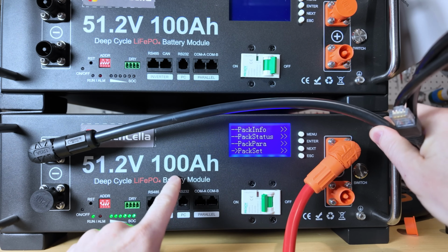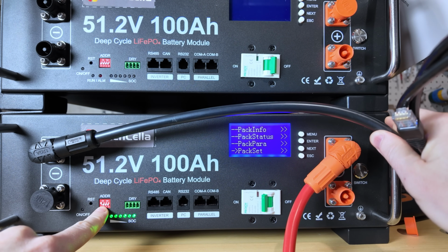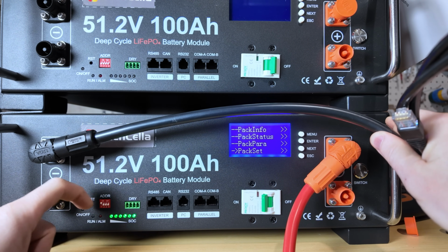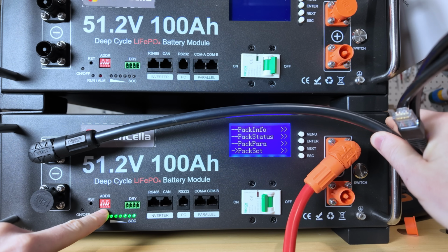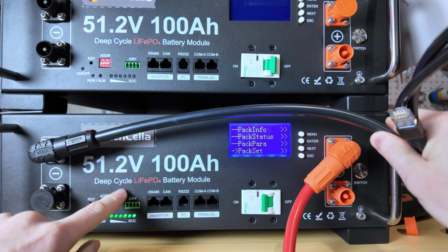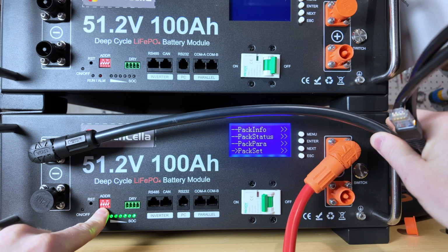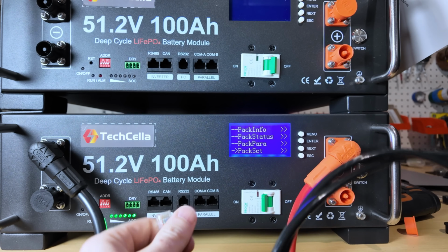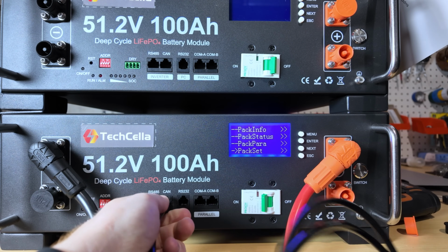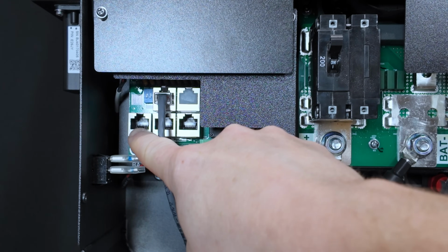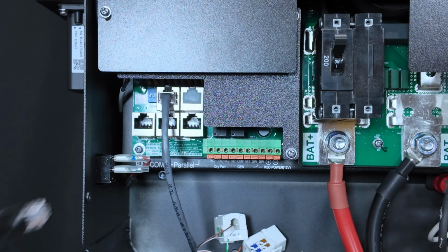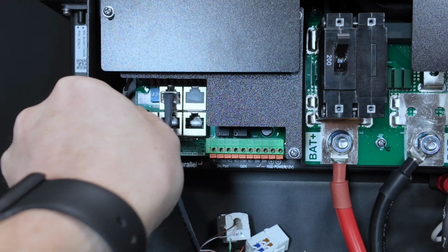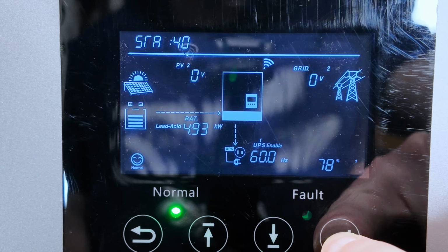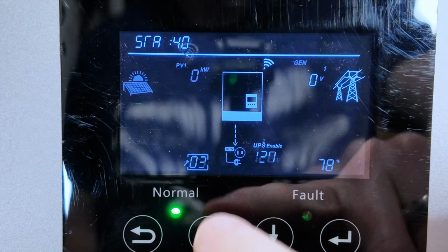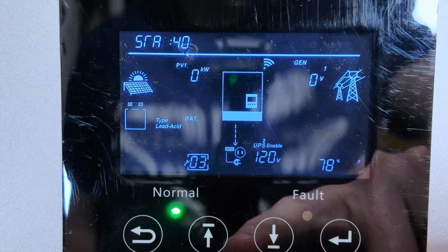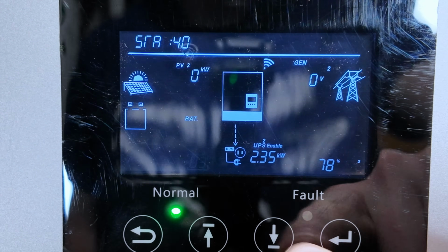Depending on how many batteries you have connected, you might need to adjust your dip switches. If it's just one, you're going to end up setting all the dip switches to down. Since we're just doing the test with one right now, we'll just set it to down. We'll take our Cat 6 cable, plug into the CAN communication port. On the inverter, we're going to plug into this bottom left battery communication port. And then on the display, we're going to go into the settings, up to option 3. Set the type to lithium ion.